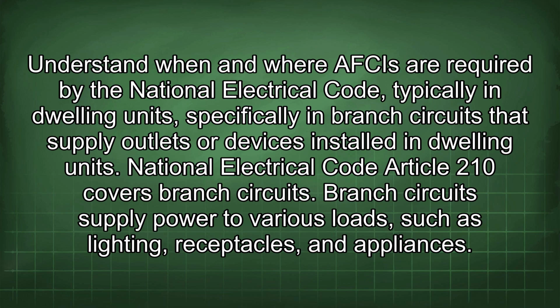Understand when and where AFCIs are required by the National Electrical Code, typically in dwelling units, specifically in branch circuits that supply outlets or devices installed in dwelling units. National Electrical Code Article 210 covers branch circuits. Branch circuits supply power to various loads, such as lighting, receptacles, and appliances.